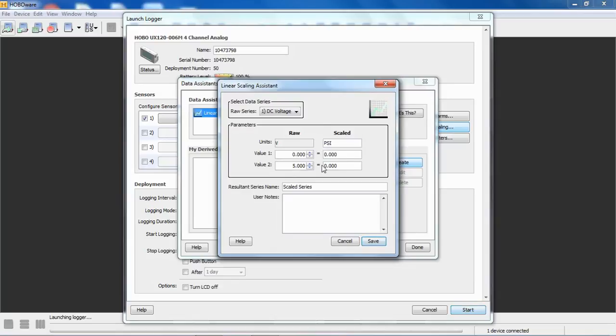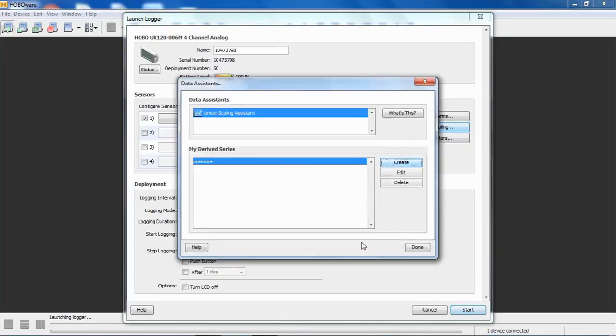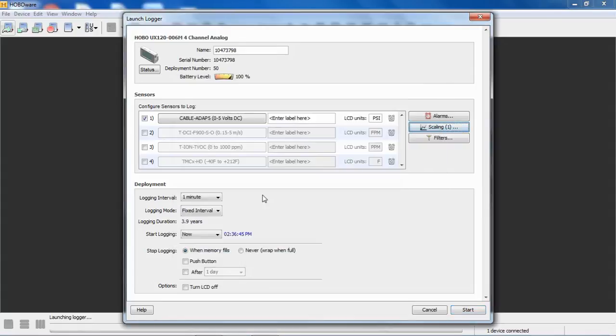pressure for our example. So we're going to say we're setting up a relationship that says 0 volts equals 0 PSI, and 5 volts coming out of that sensor equals 100 PSI. And then we can change this to pressure and click on Save and click on Done. And now you can see that we have a little 1 in parentheses, and our LCD units for this device are listed in PSI. So that's how you use the linear scaling assistant when you're launching a logger.